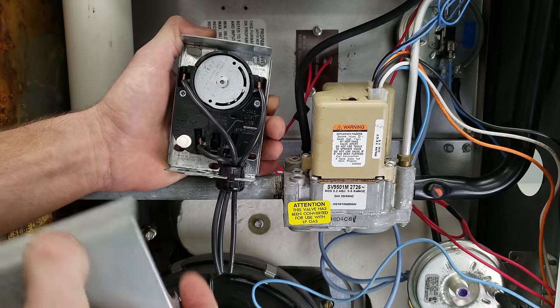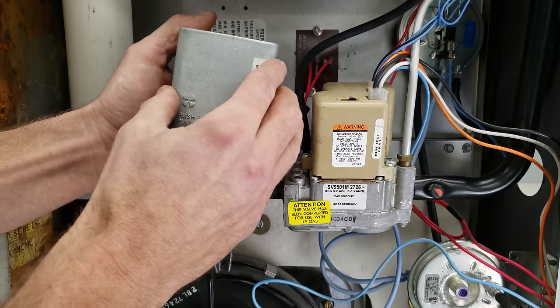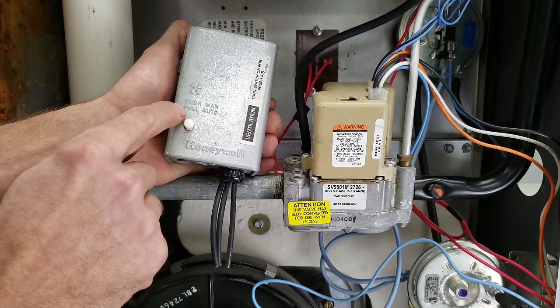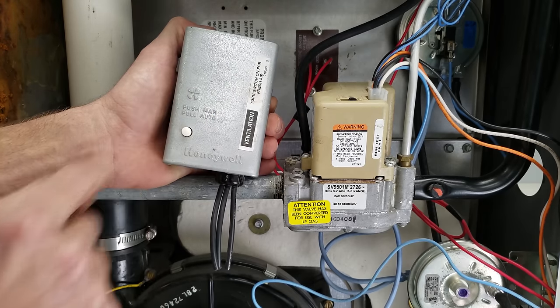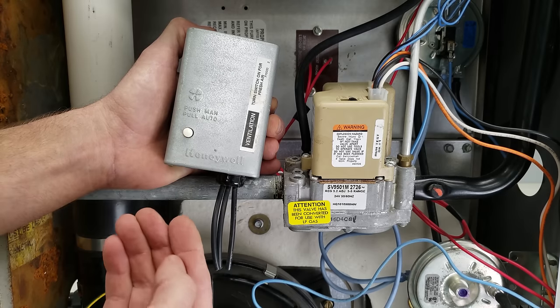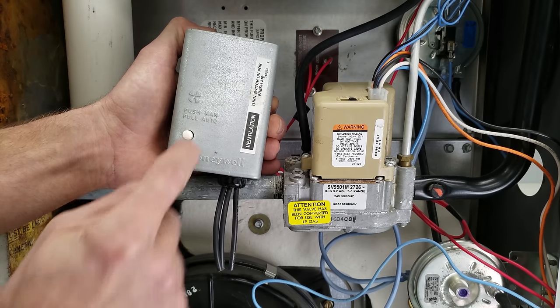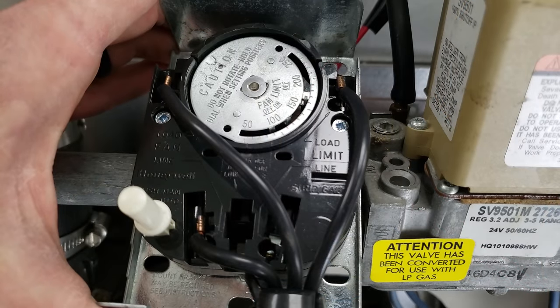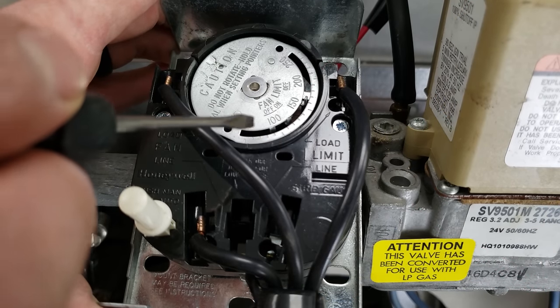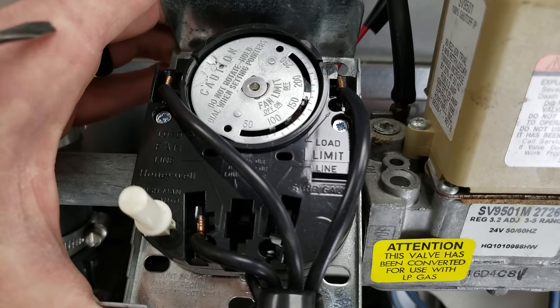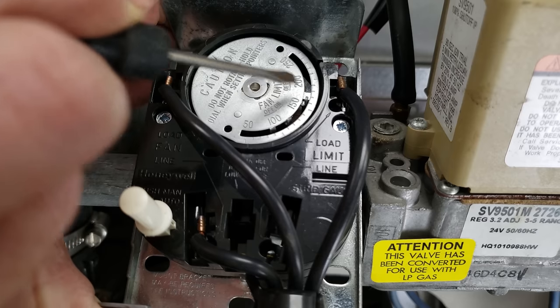So I want to take you in for an up-close view of this, but first I just want to show you some of these have a push for manual. So if that's pushed in, then the blower motor is just going to continue to run. And if you pull it out, that's what's going to keep it on auto. When you remove the cover plate, you're going to see this dial, and you're going to have three little temperature adjustments right here. The third one, that is the high temperature limit.